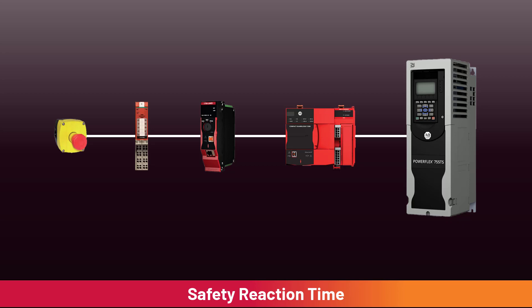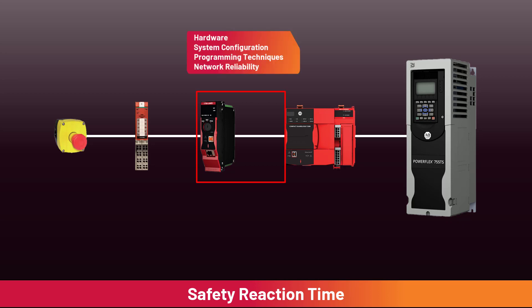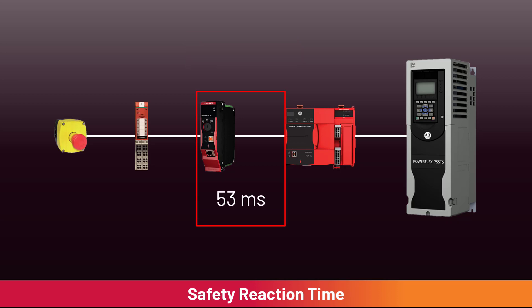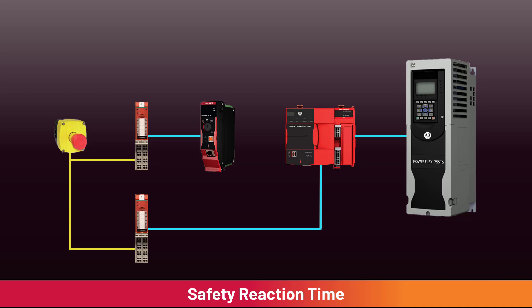A produce/consume connection adds an additional controller and a communication connection between the controllers. The amount of reaction time increase is dependent on the hardware system configuration, programming techniques, and network reliability. For this configuration, the safety produce/consume connection added 53 milliseconds to the calculated single fault reaction time — an increase of about 50% from a single controller system. If the additional reaction time added by the produce/consume connection exceeds the safety functional specification, the application may require using hardwired inputs or an input-only connection. Designing for optimum safety reaction is a topic for another video. That concludes today's lesson on safety produce and consume.